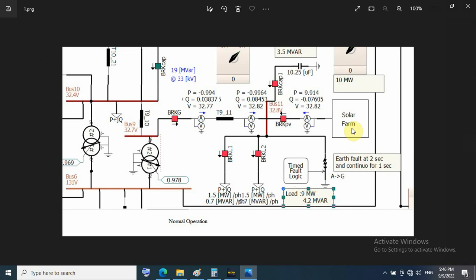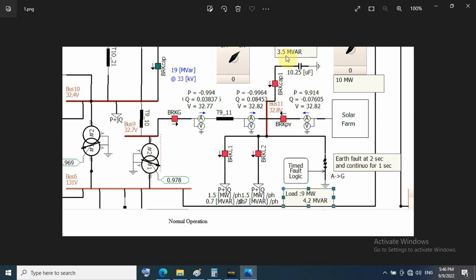Here for PV, I have 10 megawatt PV integrated at bus 11. The local load is about 9 megawatt and 4.2 megavar. Earth fault on phase A of bus 11. In normal operation, PV supplies about 9.9 megawatt. For 4.2 megavar reactive power, it will be supplied by capacitor bank about 3.5 megavar. The remaining will be from the line from grid side. The earth fault will be on bus 11 for phase A to ground.